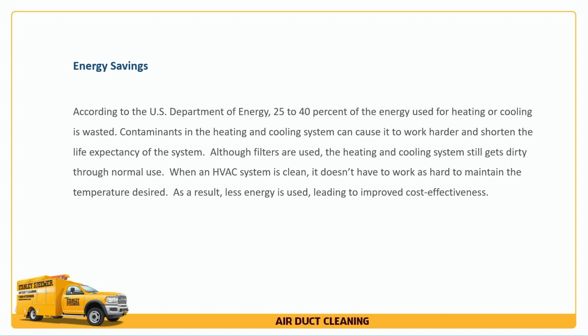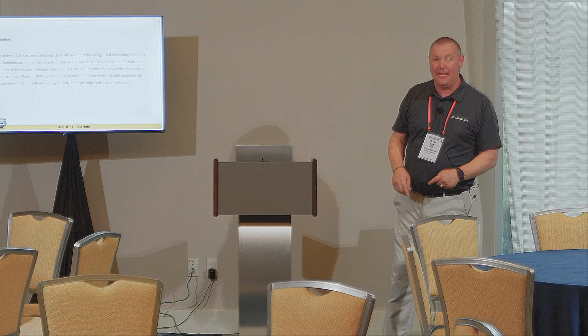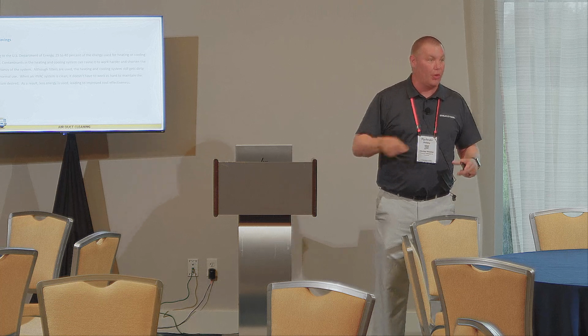Has anybody ever opened up an air handler and seen that the fins inside that wheelhouse for the fan blade are just caked? Those things are designed to have a bevel in there so they can scoop air and go. Well, guess what happens when somebody's in there saying I need to lower this, the temperature's not feeling good—a lot of times that thing is caked up, it's not moving air enough, and it's working harder.